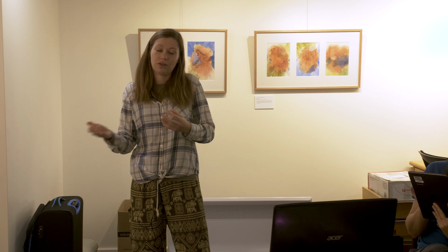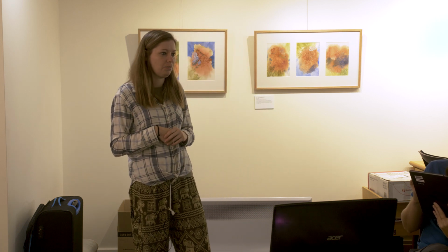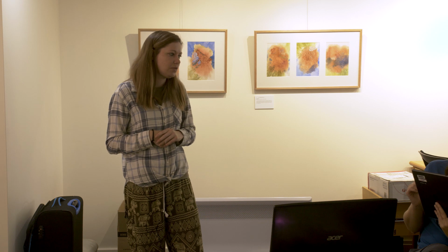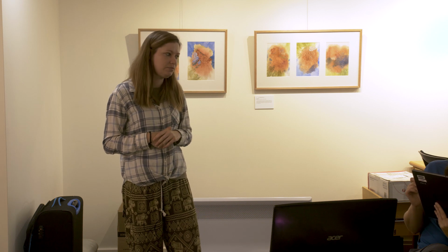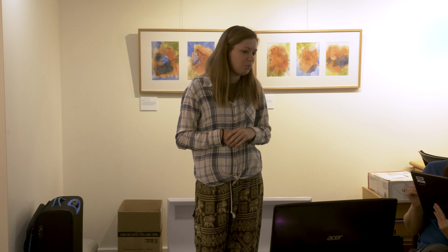So if you're interested to know more about this, I recommend to look into that table and the manual. But the default value for most surfaces that you will find anywhere really is 0.95, and that's what they recommend to use, unless you have something more specific, like a mirror that you want to take an image of and so on. Otherwise, this is the value to use. Oh wow, that's really high. Yeah, it is high. So this covers most of the surfaces. Yeah. We barely change it.